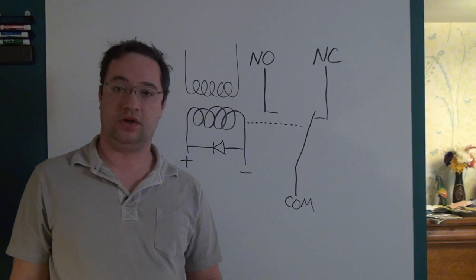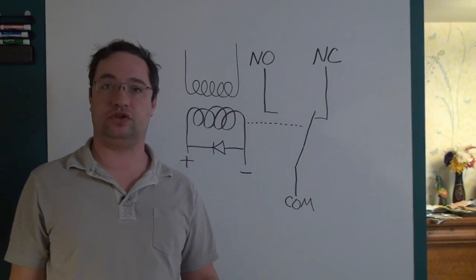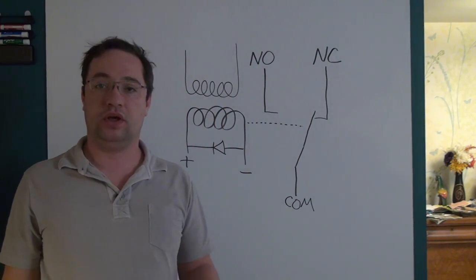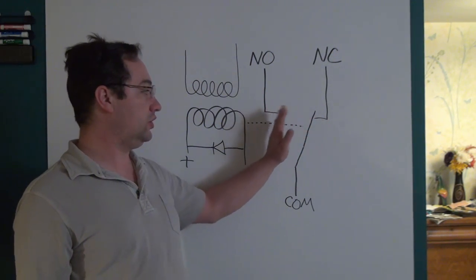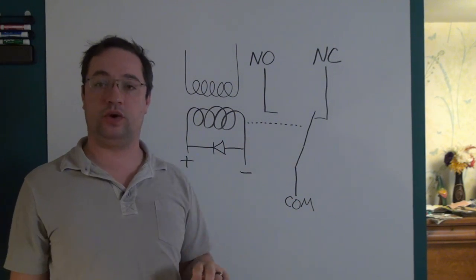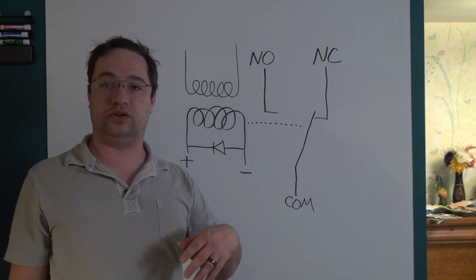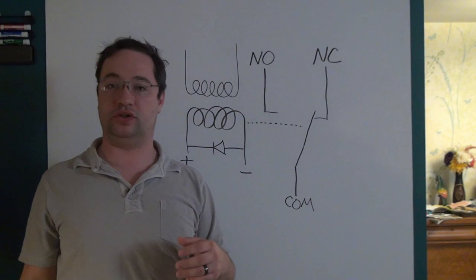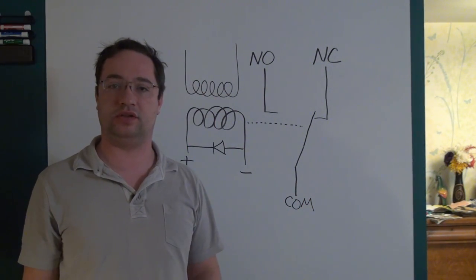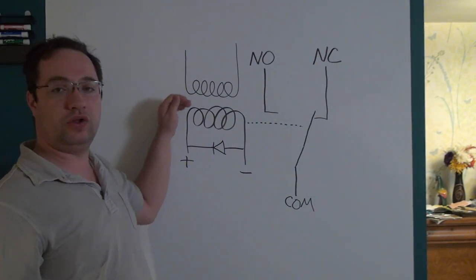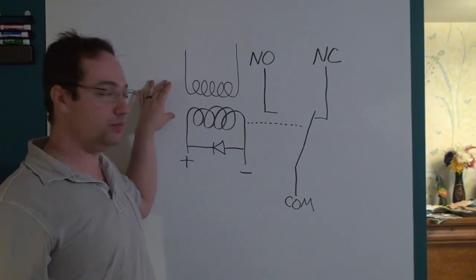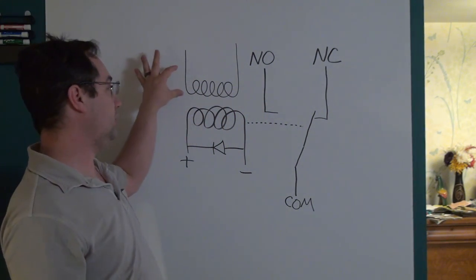Something to note with contactors: they will sometimes have two coils instead of one on the control side. The reason is that it is far easier to hold the arm once it has switched than to actually pull the arm over. So the relay has a pull-in coil and a hold coil. When both are energized at the same time, the arm comes over, but once the arm is fully over, the pull-in coil gets turned off. This saves power so the control circuitry doesn't have to be as beefy.